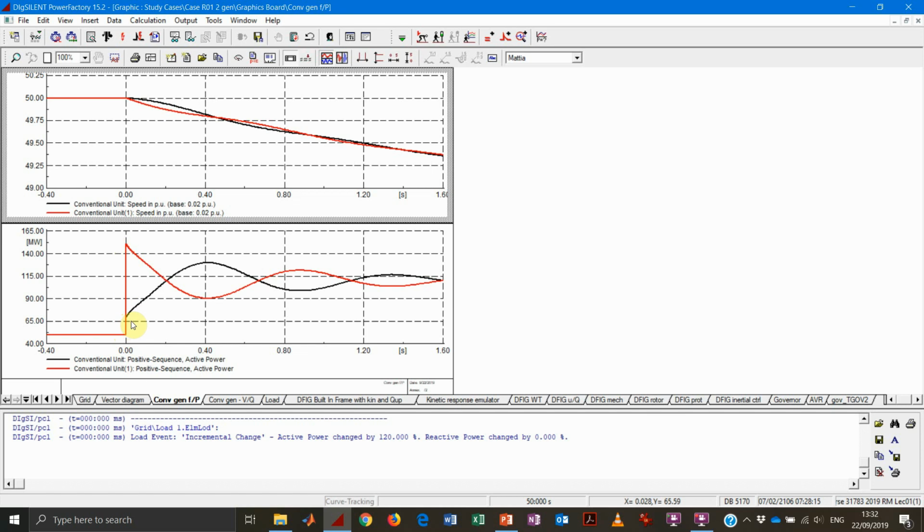So specifically, the first generator, the original conventional unit, has the two transformers and the line between itself and the load. While instead, the other machine is just connected directly to the load. So there is just the synchronous reactance, the internal reactance of the machine.